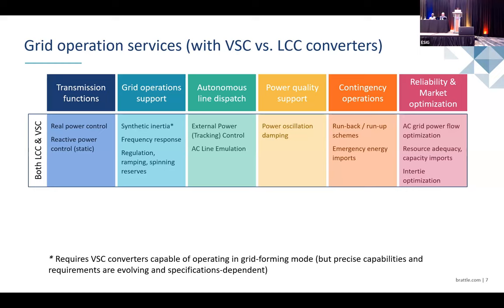That means HVDC can help compensate for disturbances in the grid, basically to make a better power system. It can improve power system operation. Similarly, for HVDC, you can manually control the power flow. Otherwise, we can also do automatic settings. For example, based on the events happening in the power system, it can derive power orders to itself, basically.